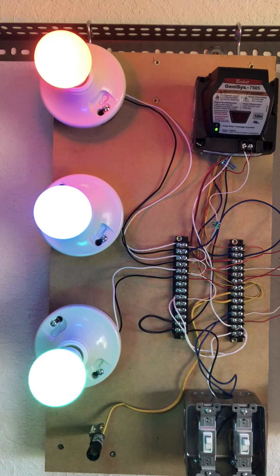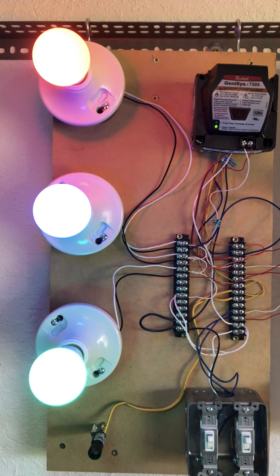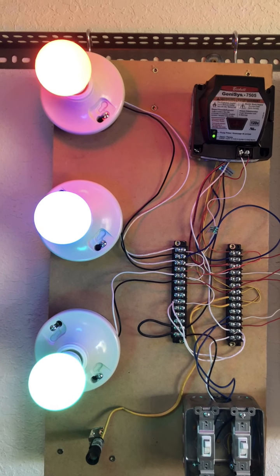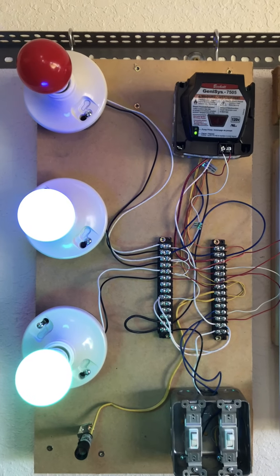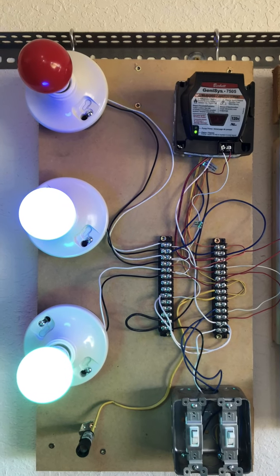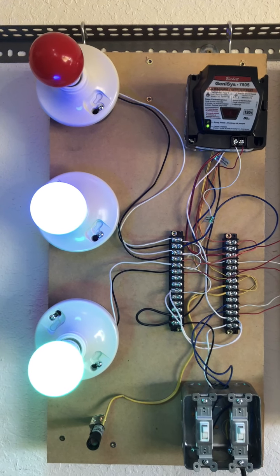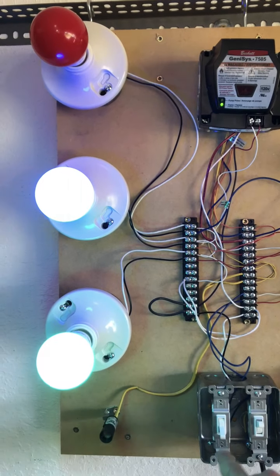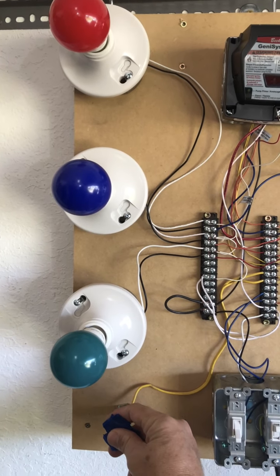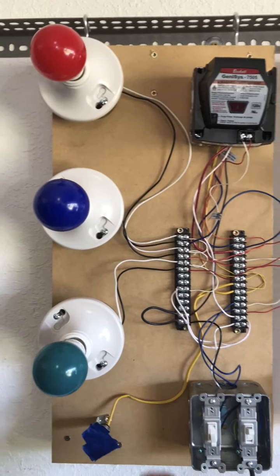Once we see light on the CAD cell, which indicates flame, eventually my igniter, which is the top bulb, is going to shut off because now I have flame. As long as I have flame, I don't need the ignition control. Now let's see, the call for heat ends. We go through this. My CAD cell is now in the dark.